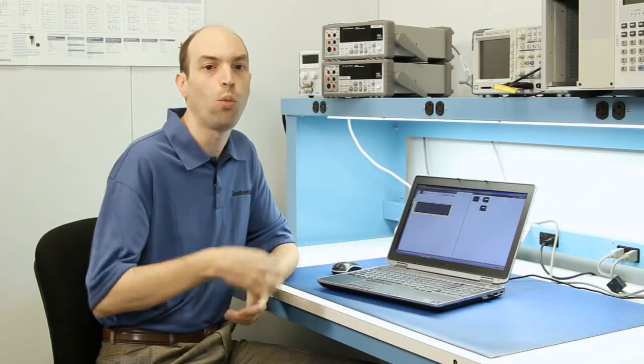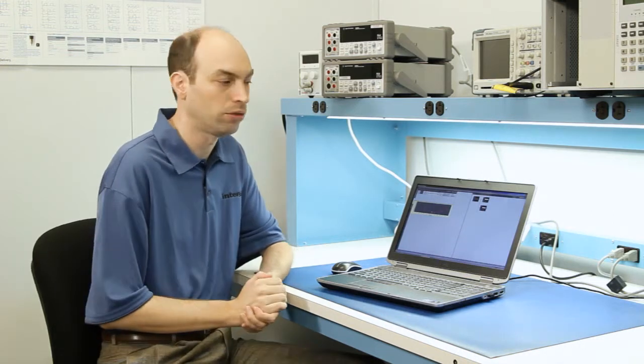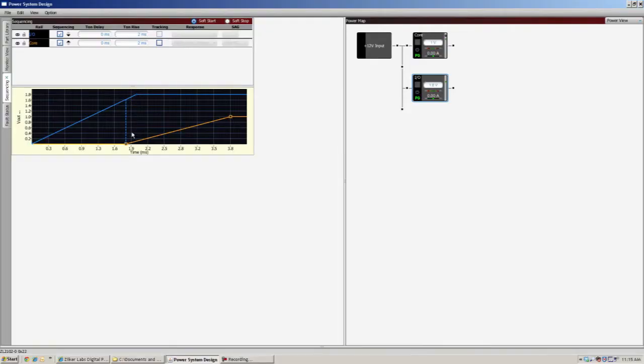So now it's event-based. It waits for the power good threshold to occur before the next rail starts. If we want to change the order of these two devices, you can use these up-down arrows. Maybe we want the core to sequence first. And now you can see once you reach the power good threshold for the core, the IO rail will start to sequence up.